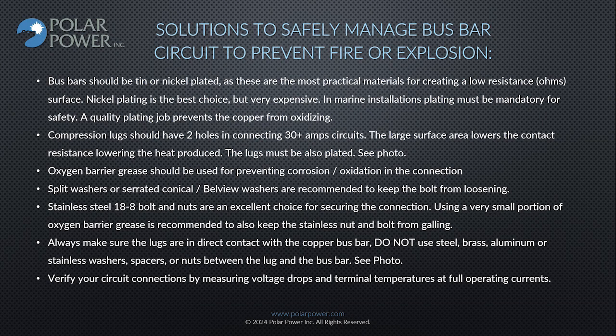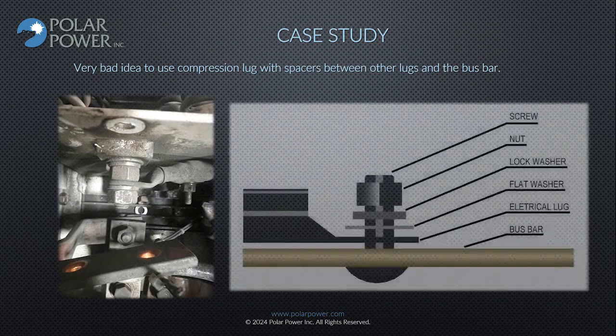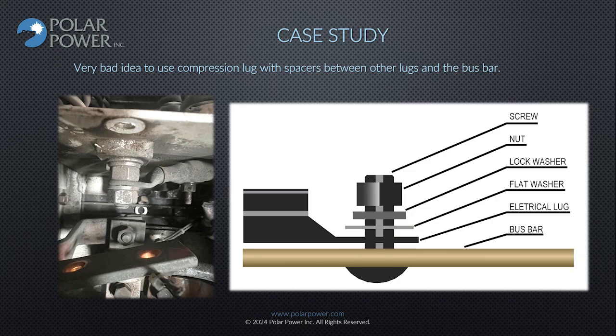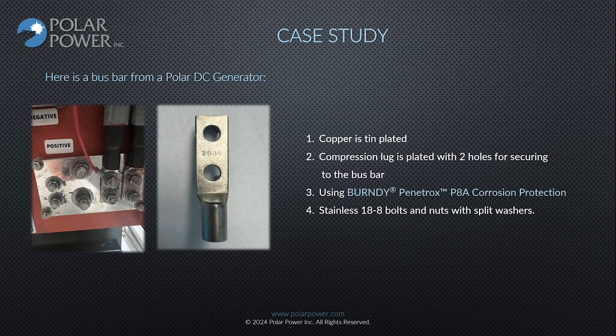Always make sure the lugs are in direct contact with the copper bus bar. Do not use steel, brass, aluminum, or stainless washers, spacers, or nuts between the lug and the bus bar. See photo. Verify your circuit connections by measuring voltage drops and terminal temperatures at full operating currents. It is a very bad idea to use compression lugs with spacers between other lugs and the bus bar. Here is a bus bar from a Polar DC generator. Copper is tin plated. Compression lug is plated with 2 holes for securing it to the bus bar. Using Burndy Penetrox P8A corrosion protection. Stainless 18-8 bolts and nuts with split washers.